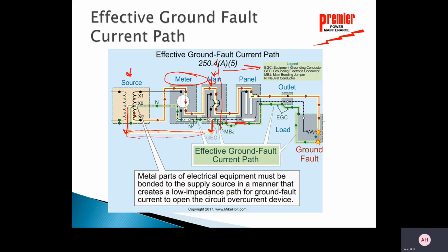But the situation here is like all of a sudden I have a ground fault over here. Now, where's the current going to flow? I have to have an effective path. It's going to go here to the case. It's going to go through that ground wire that's connected to the outlet, which goes to the next case, all the way along the way. Not one time until it got to this location did it have an option whether it wants to go back on the neutral or the ground. This is the only place it can get back on the neutral of the system. So everything from this point forward or to the load is making sure that all ground fault current goes through that grounding conductor.